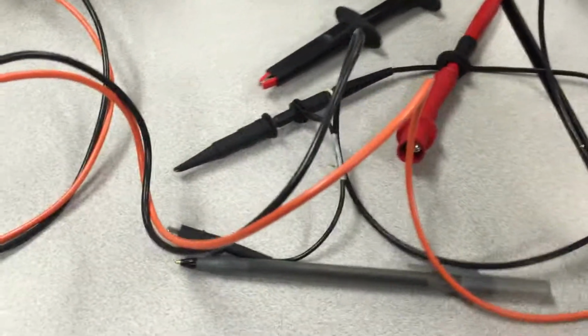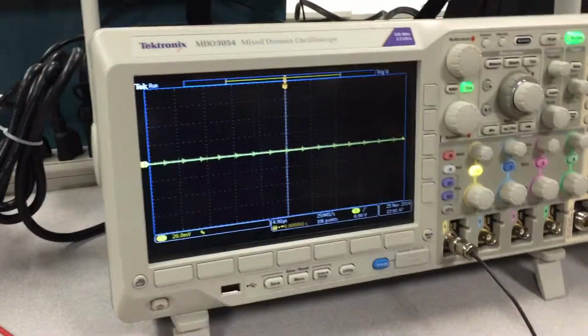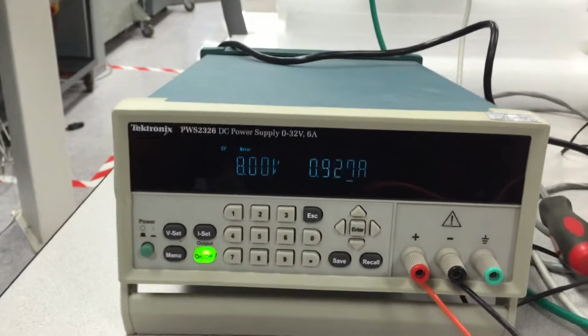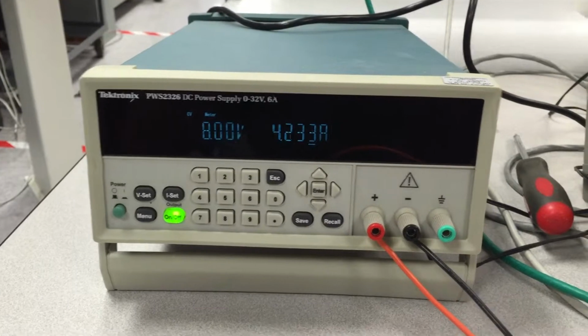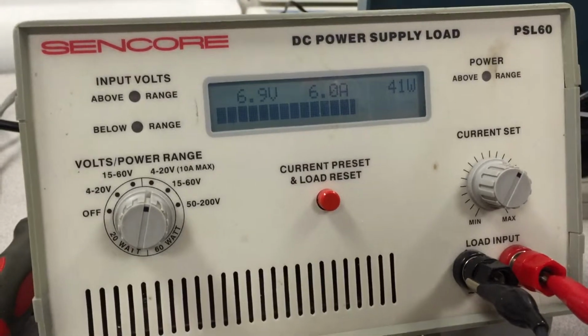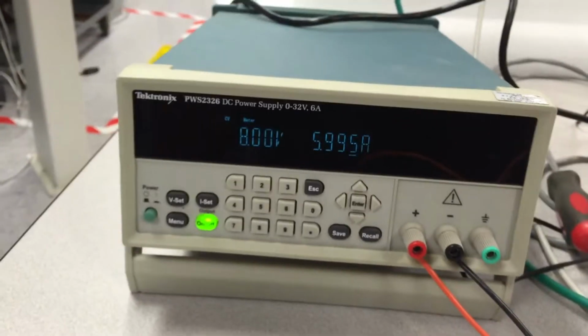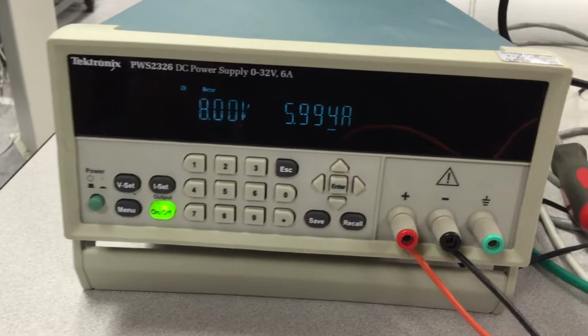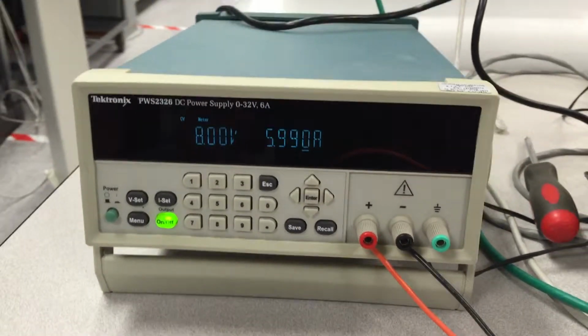So what we'll do is we'll just pass one of the outputs from the supply through the probe and connect it to the load, and we'll turn on the power supply's output. And we'll watch what the voltage measurement on the scope is. So we see the soft ramp up of the load. Right now it's configured for a load of about 6 amps. And our actual measured current on a calibrated power supply is about 5.990.